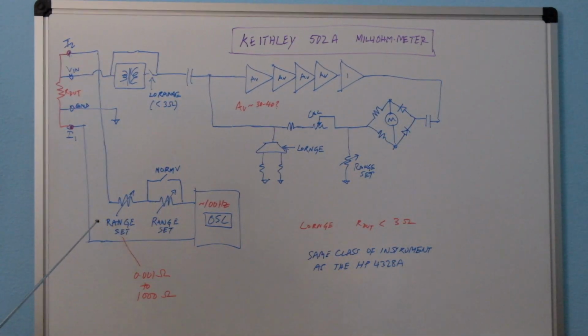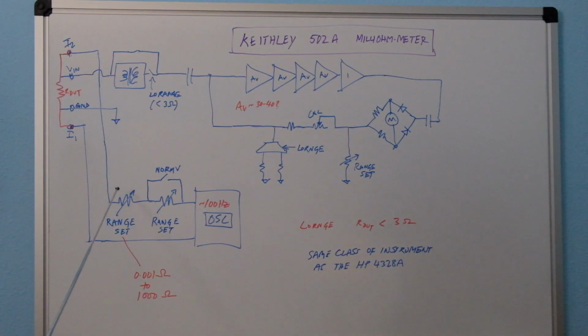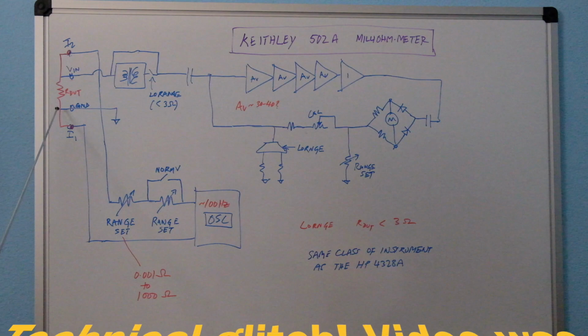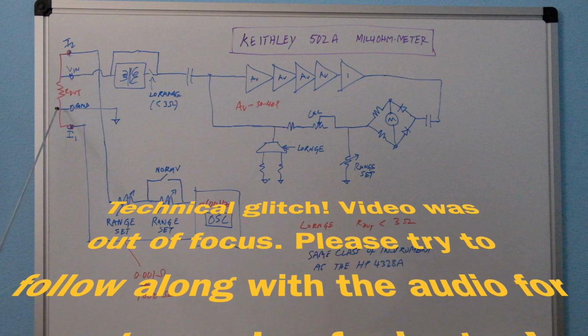But essentially the range is quite impressive, 1 milliohm to 1 kilohm, just like the 4328A, and it has a restricted voltage mode or low range mode, which can reduce the voltage developed to around 20 millivolts, I believe, for certain applications, as I mentioned earlier. The normal mode uses a higher current, and so it's probably better for measuring smaller resistances which may have a sensitivity issue.